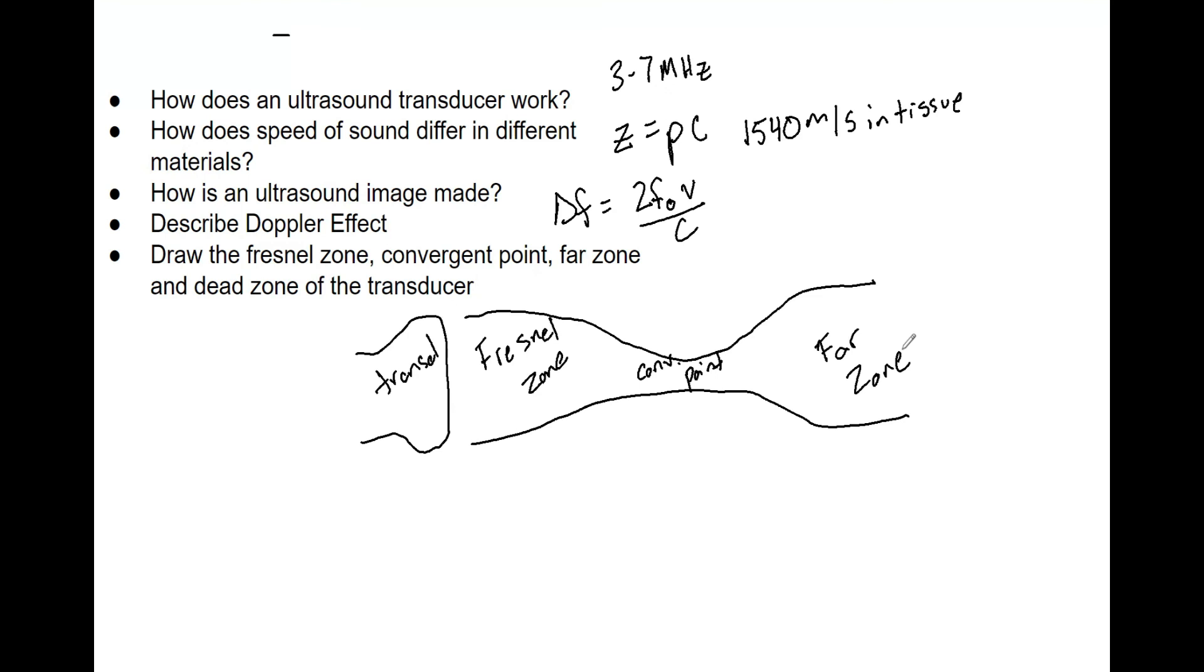The dead time, similar to other dead times, is the time it takes a transducer to stop ringing. It's the part in front of the transducer with no signal. There's a dead zone right in front of the transducer where you're not going to get signal. Very basic ultrasound information, but good for you to know.